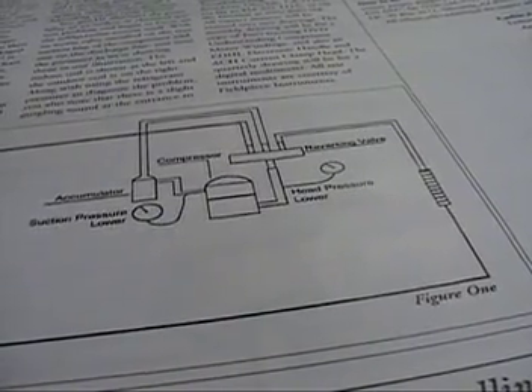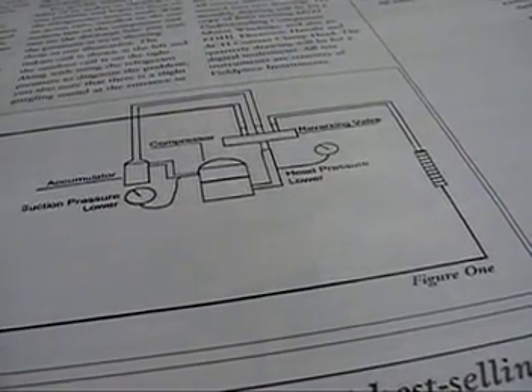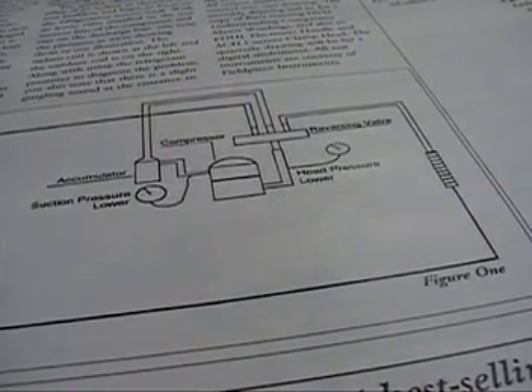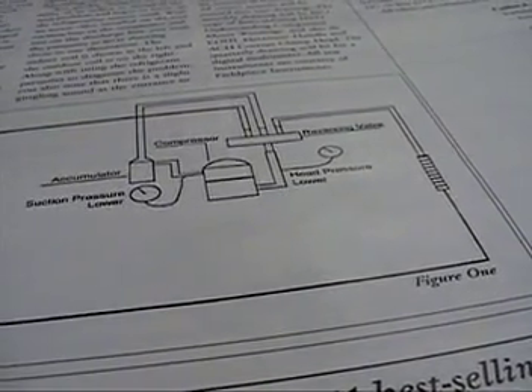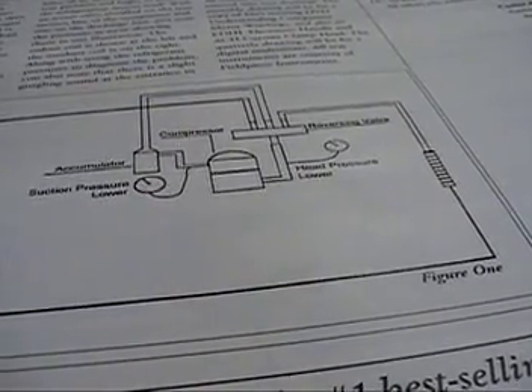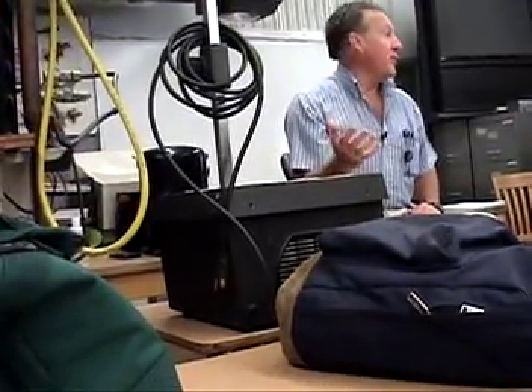Suction pressure lower than it should be, and head pressure lower than it should be. Okay, now, what are the two things that will cause head pressure to be lower and suction pressure to be lower? Restriction in the cap tube. Okay, restriction in the cap tube will do it, because there's not enough freon going into the evaporator. They said they heard gurgling. Now another thing would be low on freon, right? Low on freon would do the same thing.